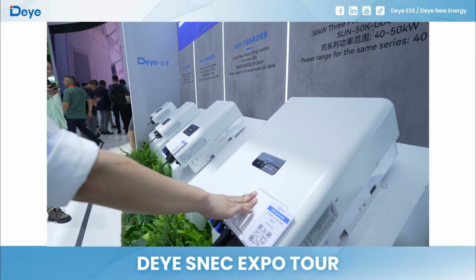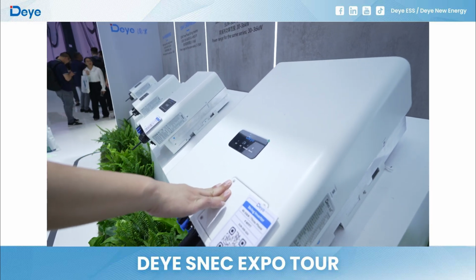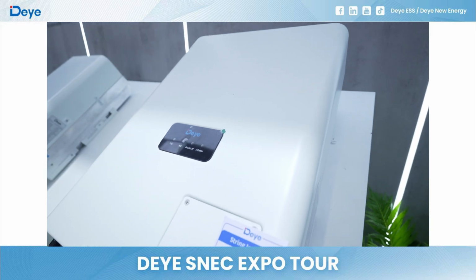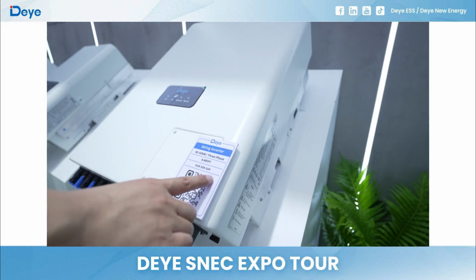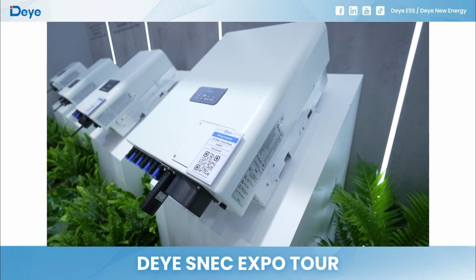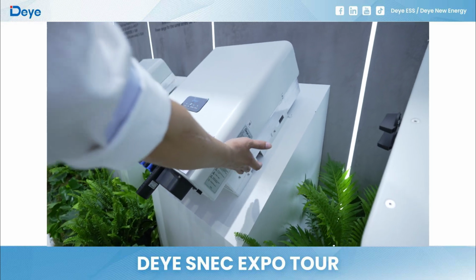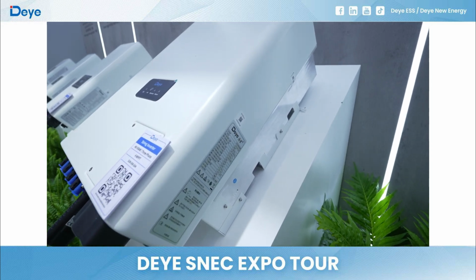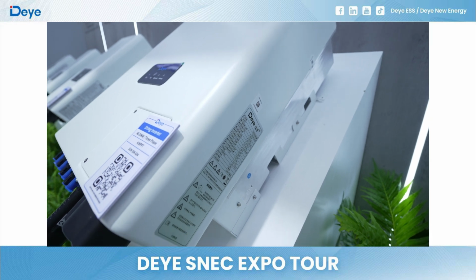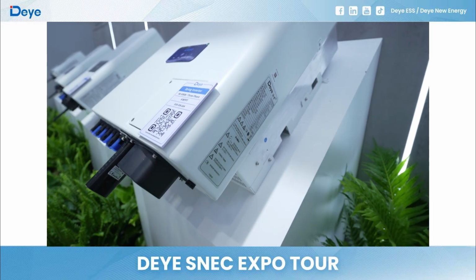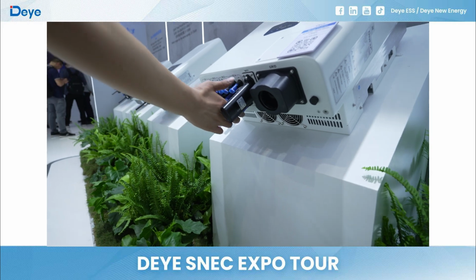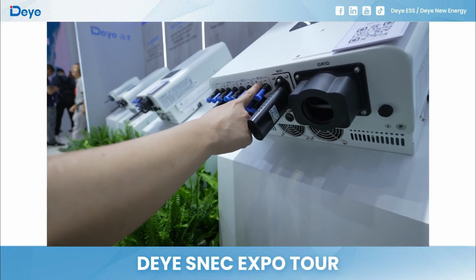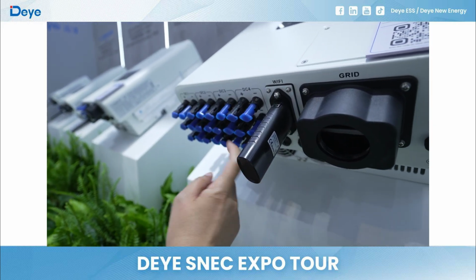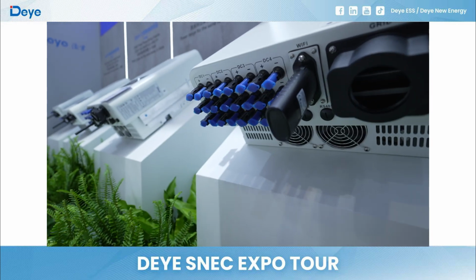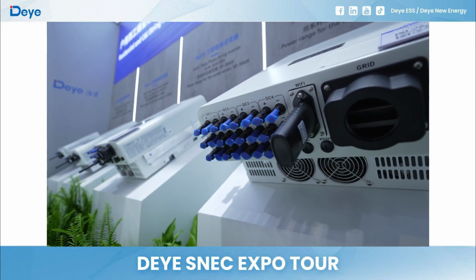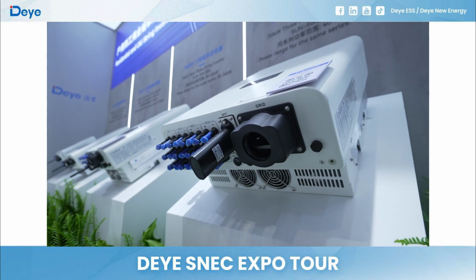And this is the 50 kilowatt 3-phase string inverter. We call it a Sun 50K G04. It has 4 MPPT. Yeah, more information we can see here. 4 MPPT. Each MPPT has 3 strings. This is MPPT4. You see, MPPT4 has 3 strings. Each MPPT has 3 strings. So in total it has 12 strings.